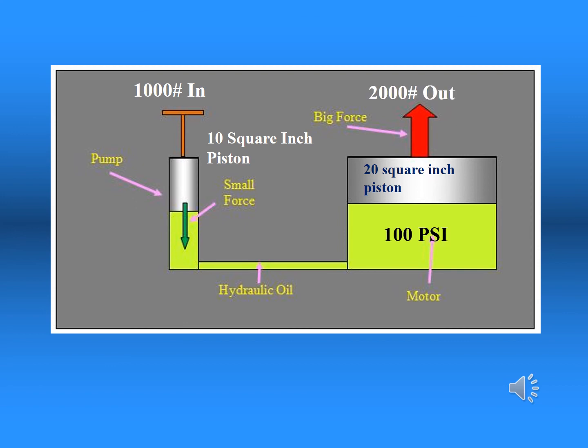This illustration demonstrates how force is multiplied in a fluid power system. At the input piston on the left, we apply 1,000 pounds of force, which is transmitted to the piston whose area measures 10 square inches. This generates a pressure of 100 psi, which in turn applies its force to the 20 square inch piston, producing an output force of 2,000 pounds. It's important to remember that pressure is multiplied times the area to calculate the force.